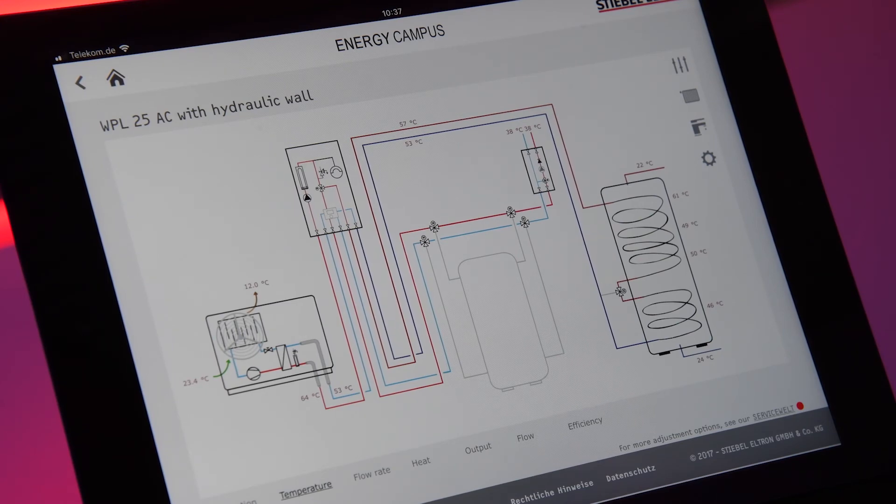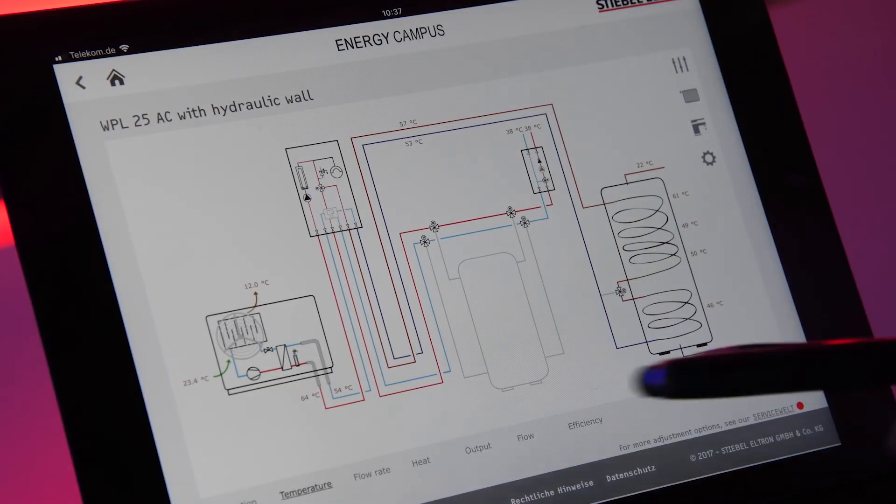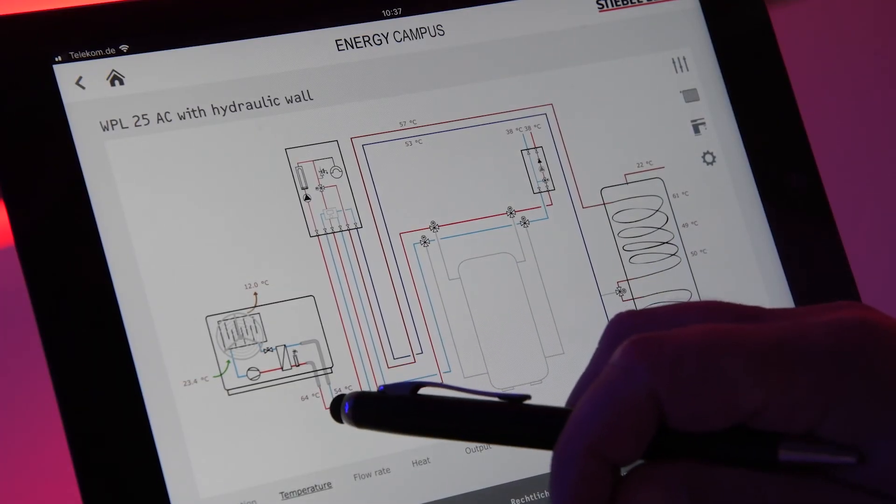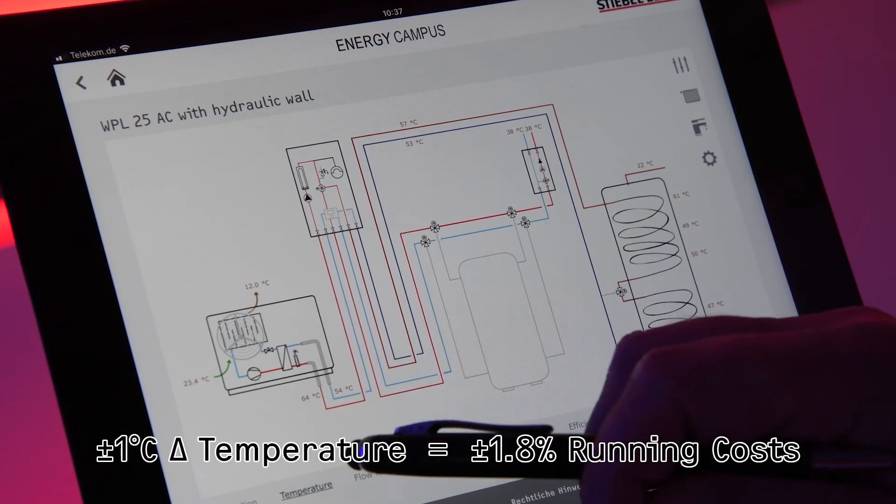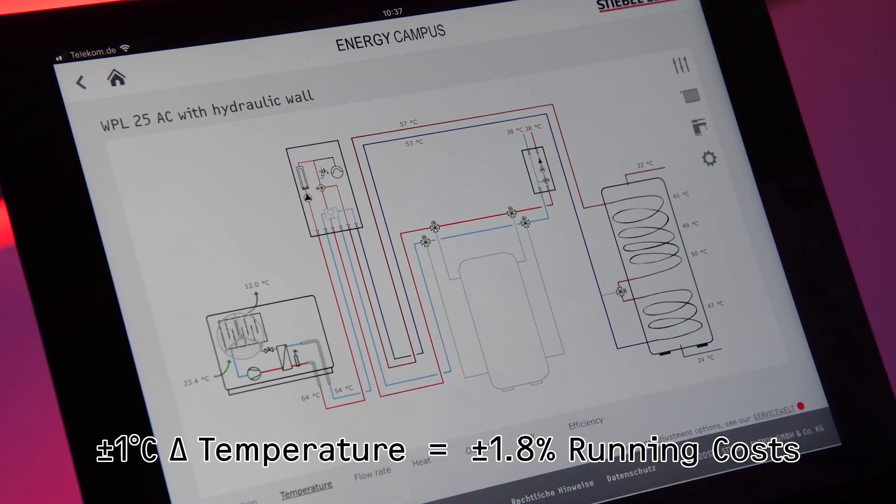The most important information is any degree C higher flow temperature you have while doing domestic hot water is increasing your running cost of doing domestic hot water 1.8%.